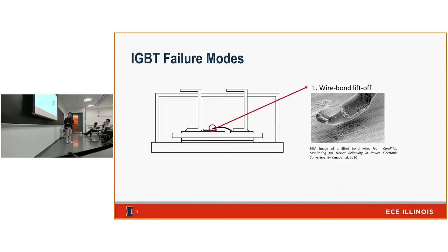Typically inside an IGBT module, you'll find a stack of different materials—the IGBT chip itself, which is silicon, different connectors or plates, and the insulating substrate, all different materials. As the IGBT module undergoes power cycling, temperatures increase while dissipating power and decrease while not dissipating as much power. This thermal cycling introduces a lot of stress in the system.